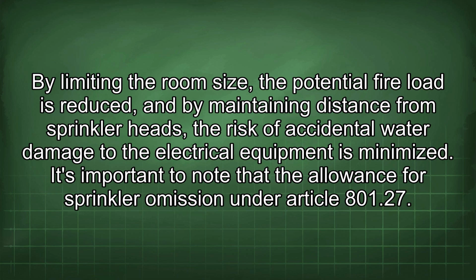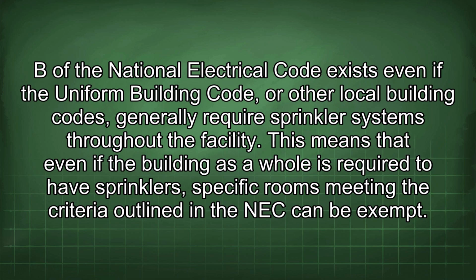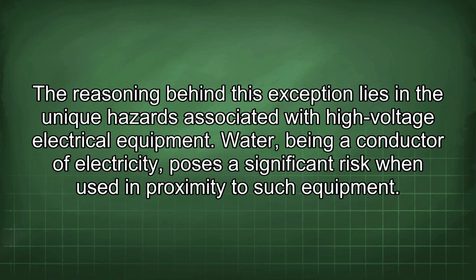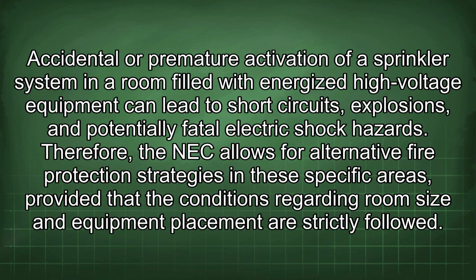It's important to note that the allowance for sprinkler omission under Article 801.27b of the National Electrical Code exists even if the Uniform Building Code, or other local building codes, generally require sprinkler systems throughout the facility. This means that even if the building as a whole is required to have sprinklers, specific rooms meeting the criteria outlined in the NEC can be exempt. The reasoning behind this exception lies in the unique hazards associated with high-voltage electrical equipment. Water, being a conductor of electricity, poses a significant risk when used in proximity to such equipment. Accidental or premature activation of a sprinkler system in a room filled with energized high-voltage equipment can lead to short circuits, explosions, and potentially fatal electric shock hazards.